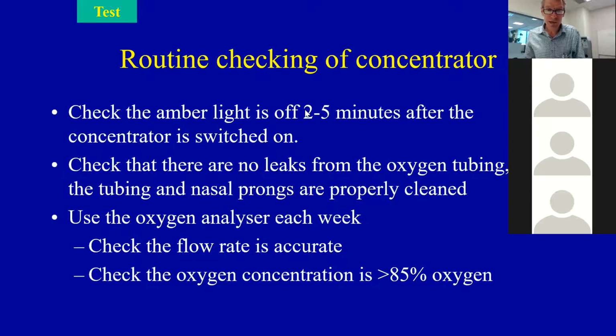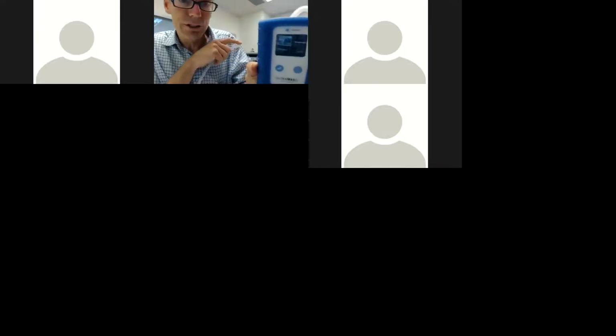As I said, you need to check the amber lights are off 2 to 5 minutes after the concentrator turns on. You need to check there are no leaks in the oxygen tubing and that the nasal prongs are properly cleaned. And you need to use an oxygen analyzer. Now that brings me to the oxygen analyzer, and I said that I'd explain what they are. I'll just show you. This is an oxygen analyzer. It looks a bit like a pulse oximeter, but it's not. These devices are very important. If you've got an oxygen concentrator, then I think you really need to have an oxygen analyzer.